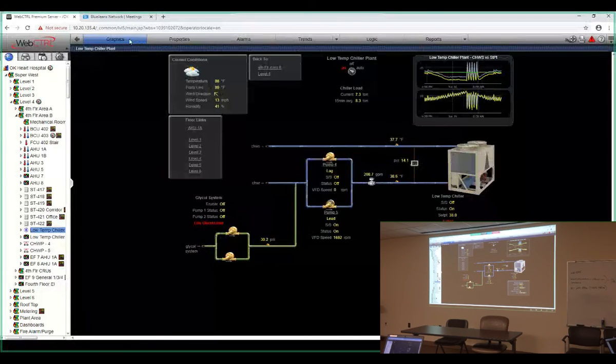Help me understand what the glycol pressure is about. When the system pressure, the chill water pipe system pressure, gets below 30, we fill the system back up to 30. Why would it do that? It's closed loop. I don't know. Scott, you know? I just want to make sure I understand. Once you've got it filled up and everything's good, it shouldn't vary unless you had a major leak or a blowout strainer or something. I mean, it shouldn't vary that far.